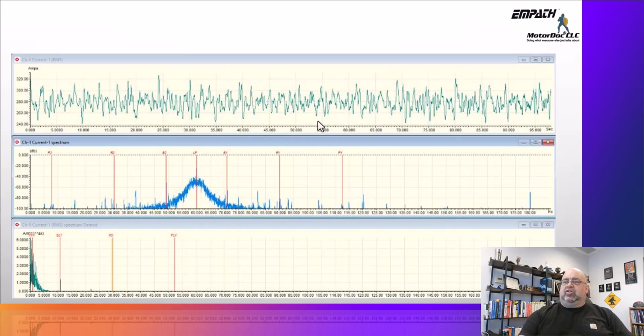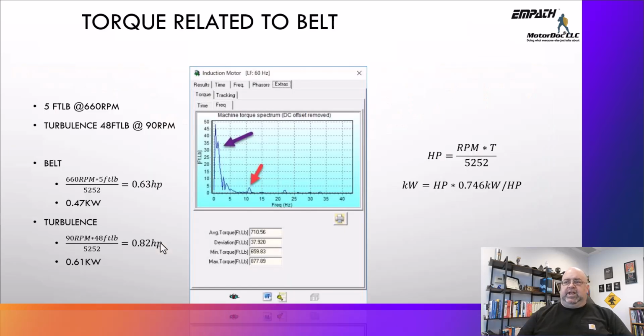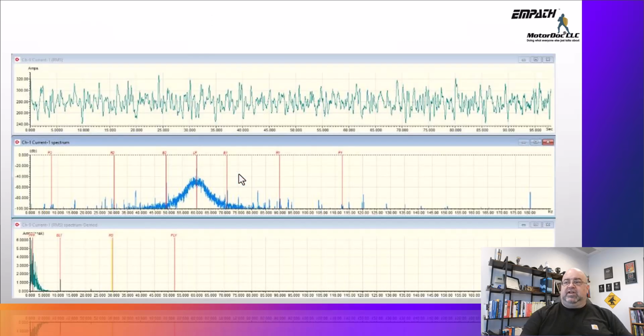Okay, so if I go in and I take a look at this machine, and this is a belted application, I see a belt signature. It's no belt flapping, but this is a belt signature, so there's something going on there. And I look at the air gap related stuff, and by the way, there's some turbulence involved. Now, I can actually do some stuff if I just have torque. Okay, torque is, well, let's put it this way. I need to know the exact frequency that I'm considering. If it's 660 RPM, that's there. If it's a lower RPM, like this is 90 RPM down here, I calculate it from there. So 660 RPM, 5 foot-pounds divided by 5252 gives me horsepower. I convert that over by multiplying that by 0.746. That gives me 0.47 kilowatts. That's the loss because of this belt frequency right here.